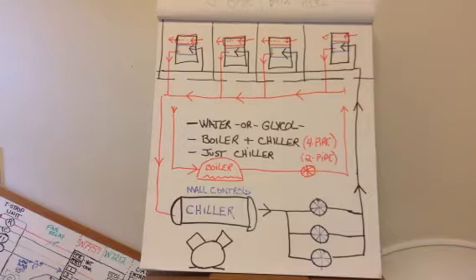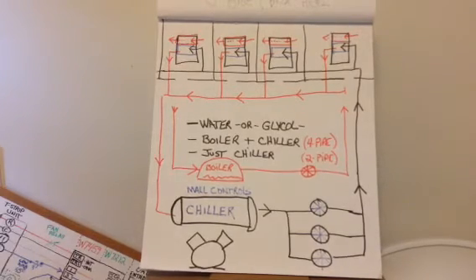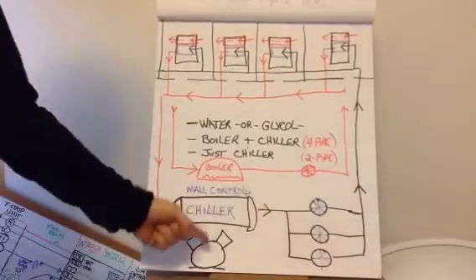So it gets a little bit complicated there, but pay attention to what the mall has before you start messing with controls. If you don't know what is in the pipe, whether it's chilled water, hot water, or a combination, then don't start changing controls and wiring until you understand the system, is what I'm trying to get at. So again, the mall controls this and this.